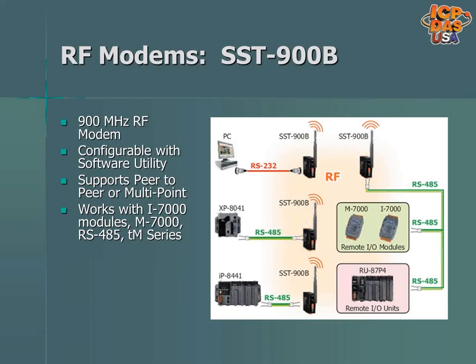SST-900B operates over the 900 MHz band, supports peer-to-peer and multipoint topologies, and RS-485 and Modbus RTU devices. A PC or controller like the XP-8041 or IP-8441 can be connected to an SST-900B RF modem, and it can communicate wirelessly to I/O modules or I/O racks if another SST-900B RF modem is connected to them and is configured to be in the same network. If an environment has a lot of Wi-Fi networks and ZigBee devices, 2.4 GHz devices may not work well if added, so 900 MHz devices would be better since they would have less interference in the wireless band.